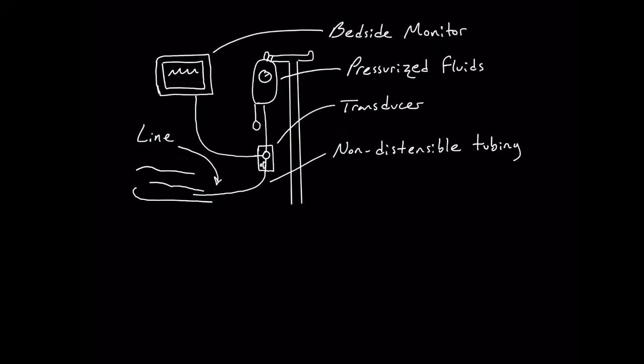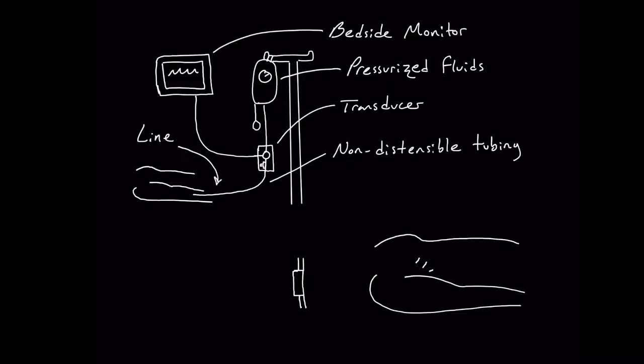In order to ensure proper readings, the system must be leveled and zeroed. The transducer should be leveled with what's referred to as the phlebostatic axis, which can be found using a level. The phlebostatic axis is the intersecting line from the fourth intercostal space mid-axillary line.